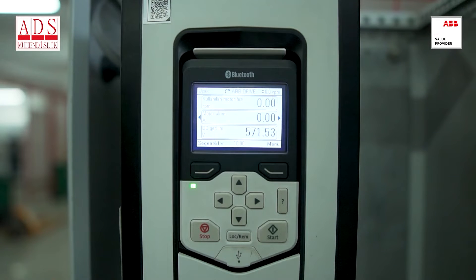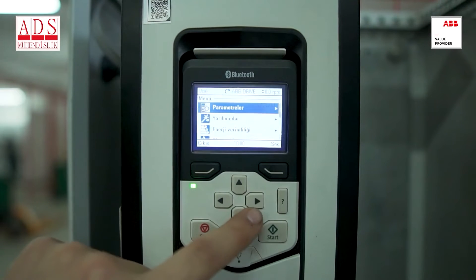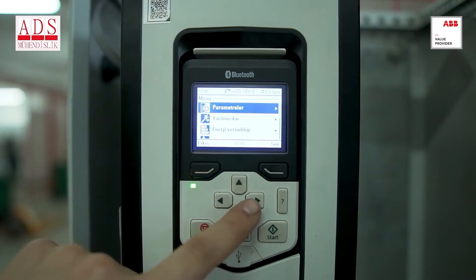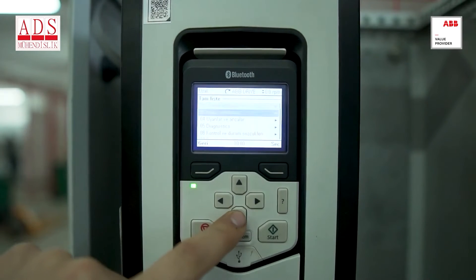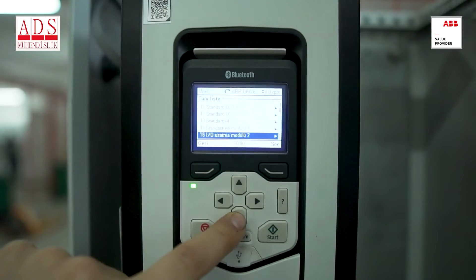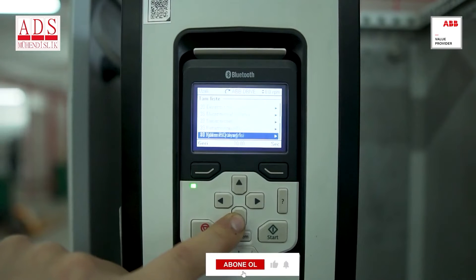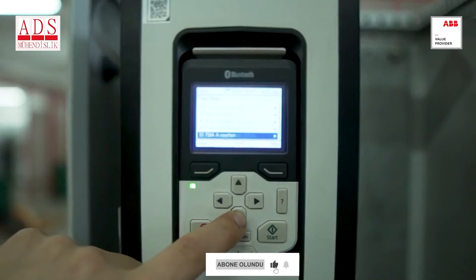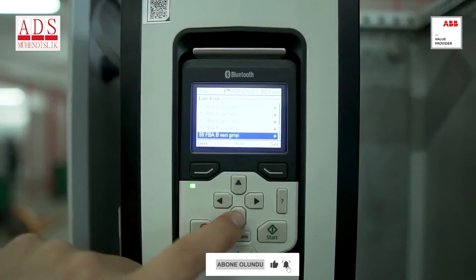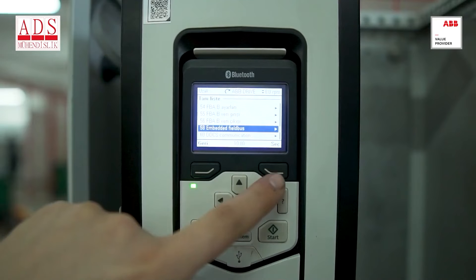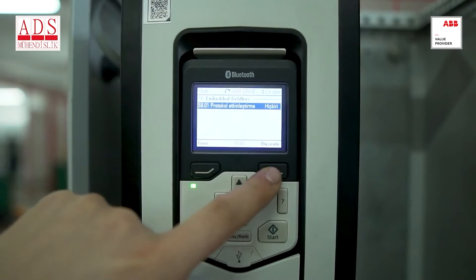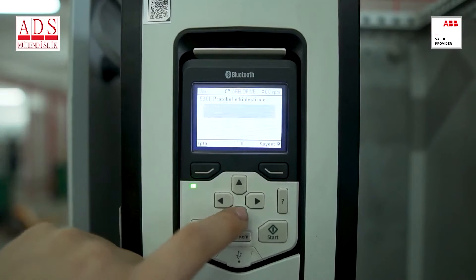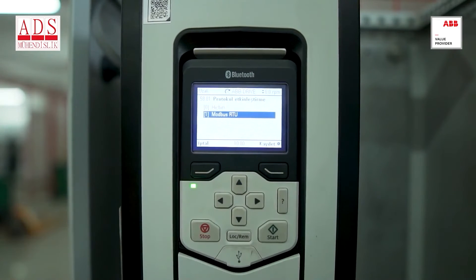To configure internal Modbus settings, we need to access the menu, parameters, and the section that displays the full list of options. Then we should locate and select group 58 from the available choices. In this case, we are opting for the internal field bus. We opt for Modbus RTU by enabling the protocol.